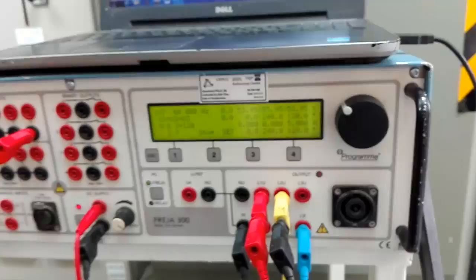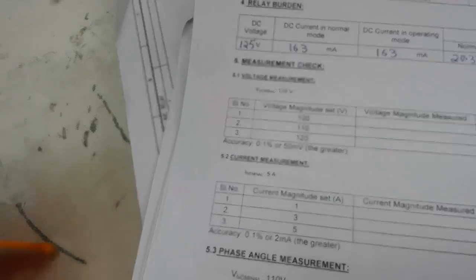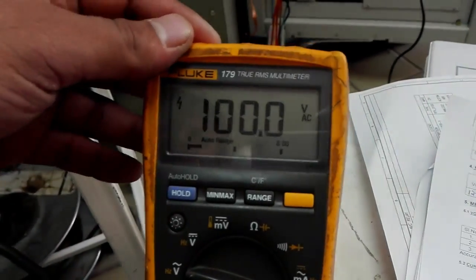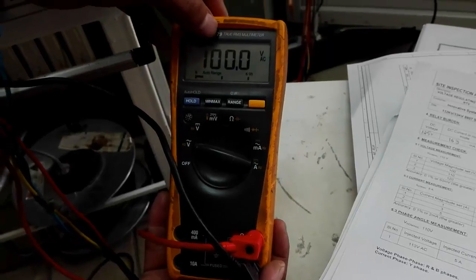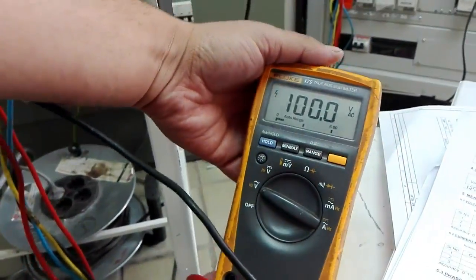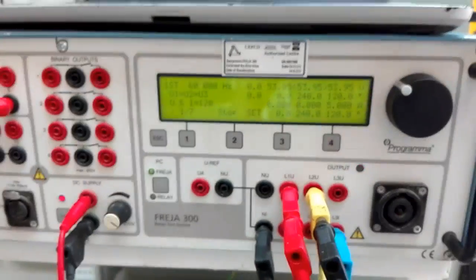So now this arrangement shows you the 100 and 110 volt AC. You can see it here through the multimeter, 100 volt AC. Now through FREJA we applied 100 volt AC. Now we will go to our ZIV relay and note the reading. Yeah, ZIV relay.